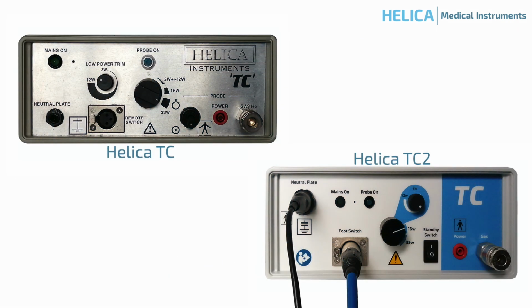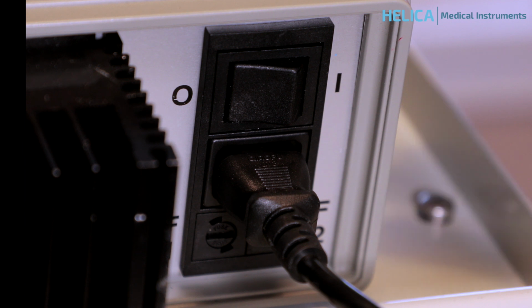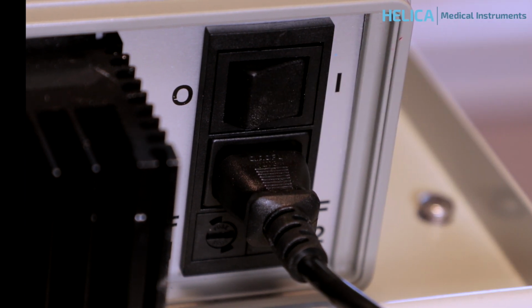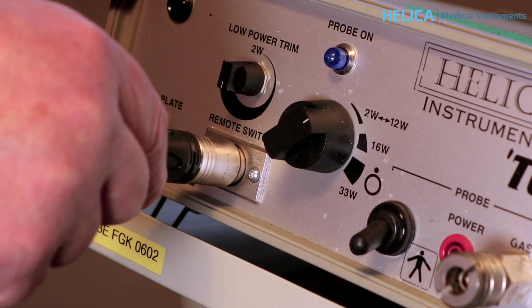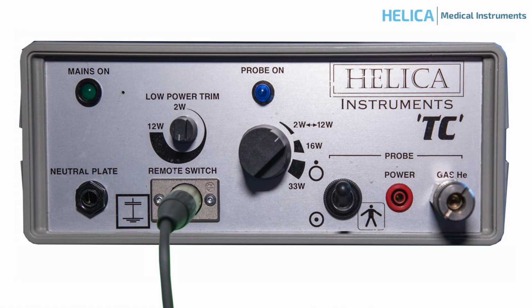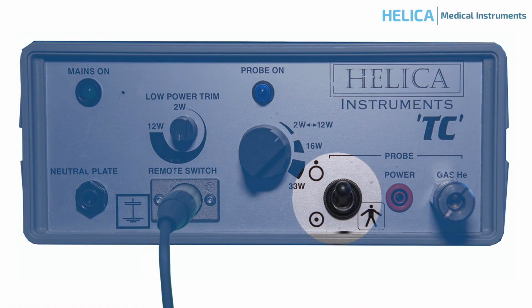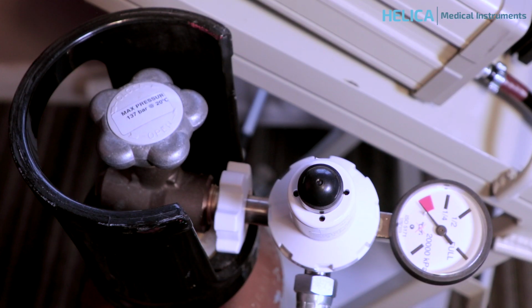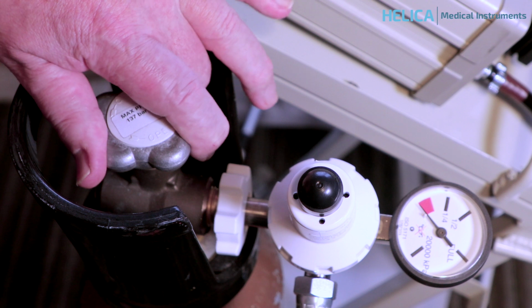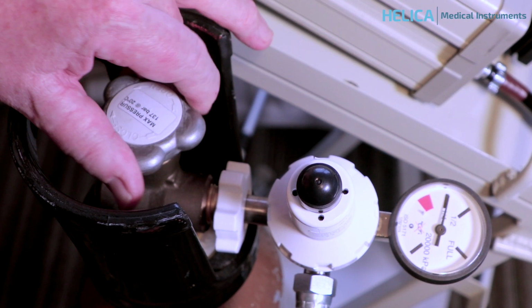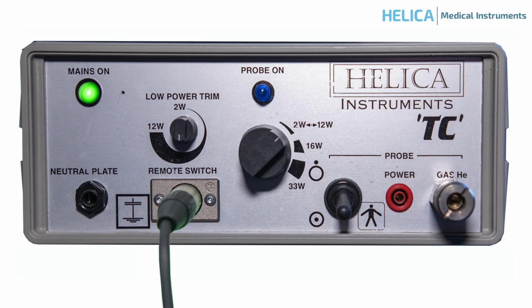When the Helica thermal coagulator has been switched on and is ready to be used, it's important to check that the controls are all in the correct positions for laparoscopic procedures. Firstly, switch on the machine. It should be plugged into a standard 240 volt electrical socket. Ensure the foot switch is plugged into the device. On the front of the machine is the standby switch, which should be turned on. Then switch on the gas by turning the key anti-clockwise about half a turn until the needle indicates gas flow. A green light indicates the machine is on and ready for use.